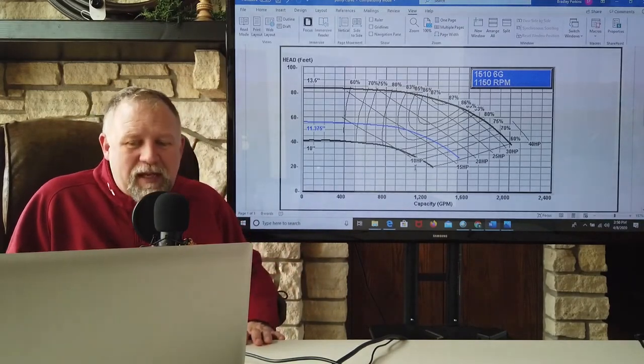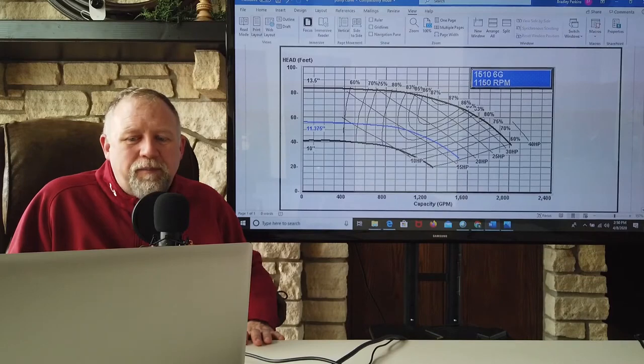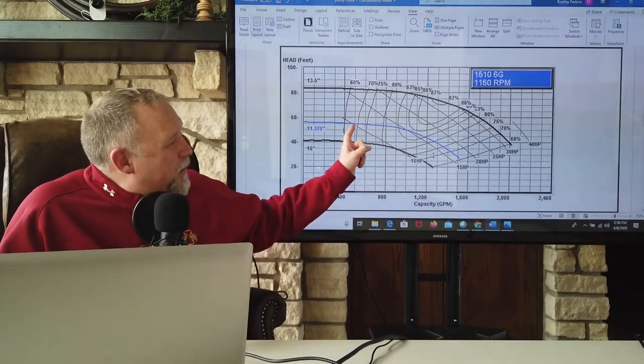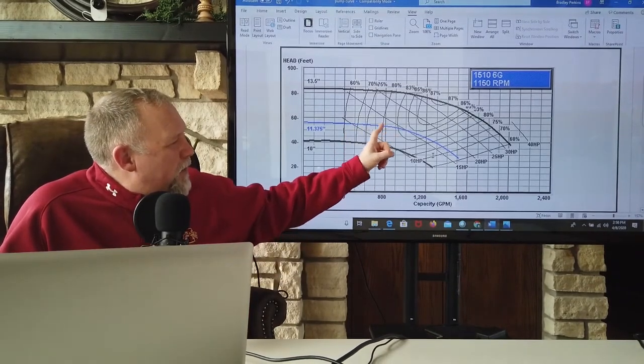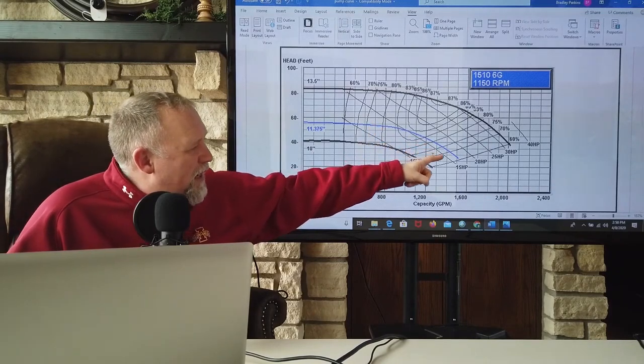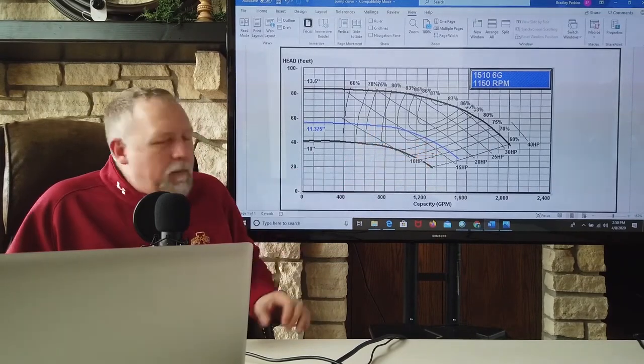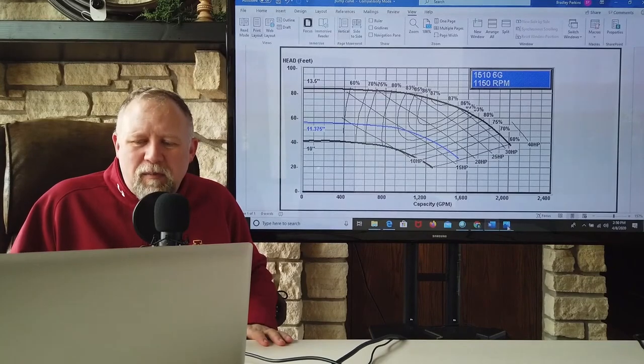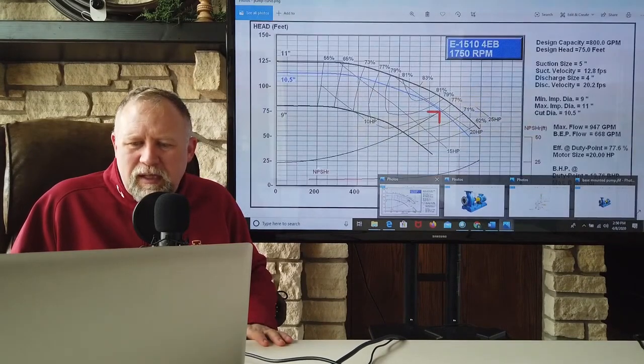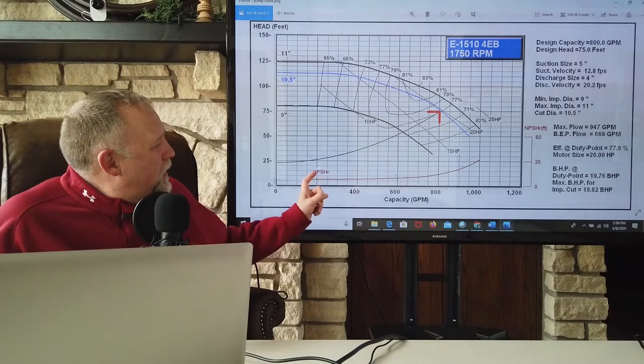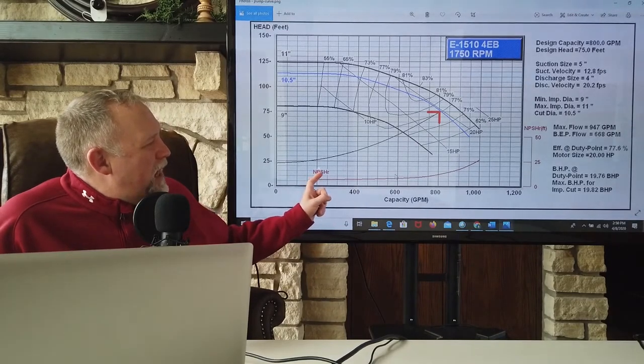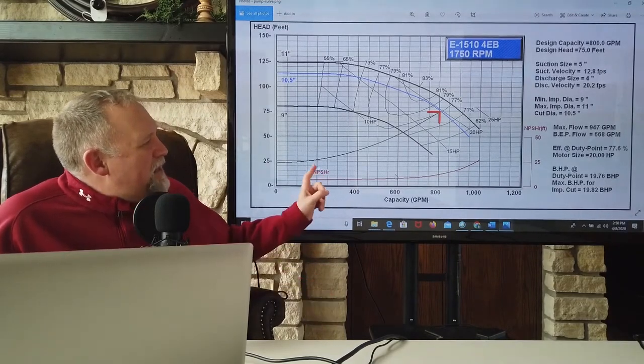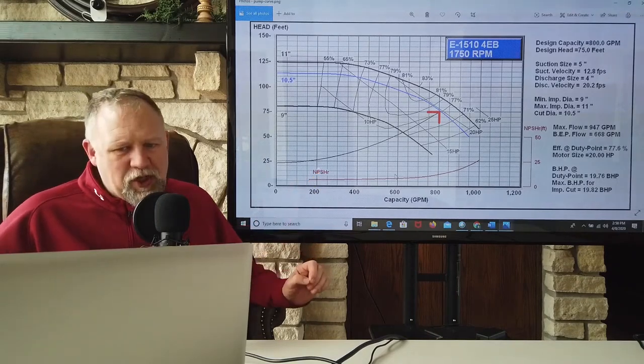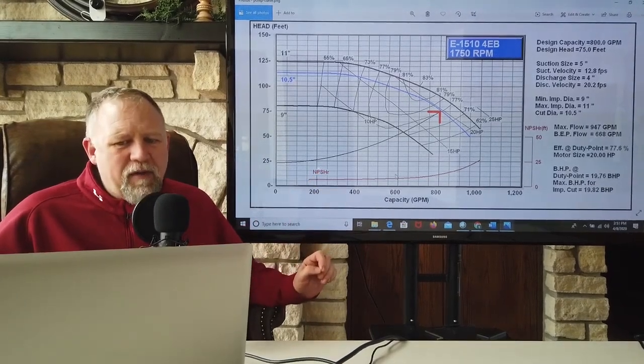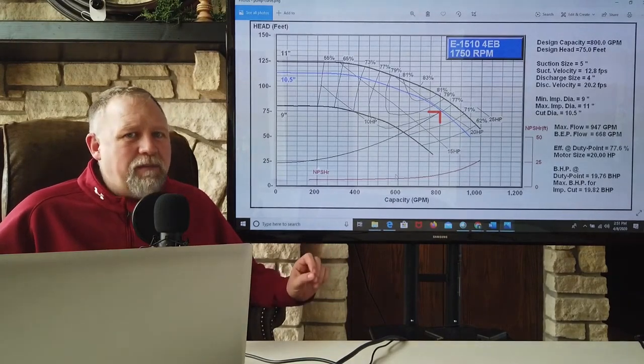Now, there's something worse that can happen than that, actually, as well. What can also happen is if we really, really overestimate it and we end up going too far down on this curve, what we might run into is a term called net positive suction head required.